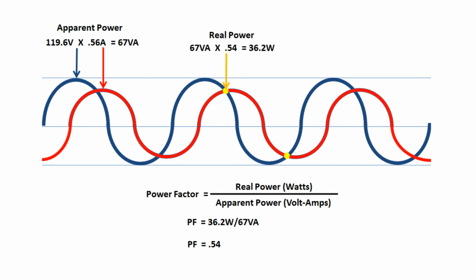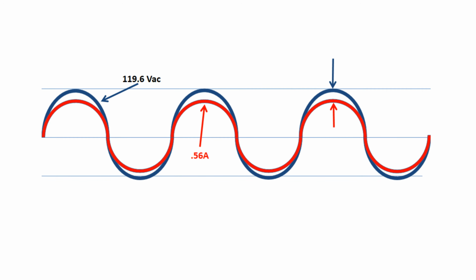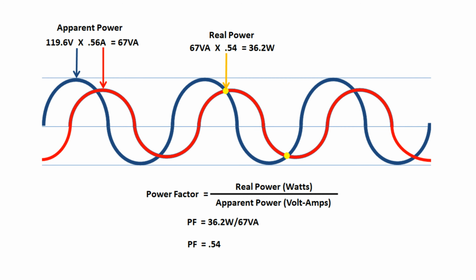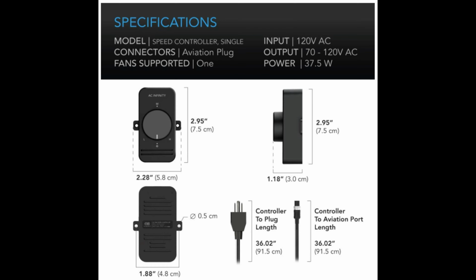The difference between apparent power and real power is basically just some wasted energy, because it doesn't do work. The higher power factor you have, the better. It's more efficient. But the important lesson here is that we always use volt amps when we're calculating loads for our AC circuits, because watts aren't always a good indicator of the current in the circuit. And the product specs I was using at first didn't provide the information I need, which is amperage. So the only good way to size this fuse is to measure the motor's actual high-speed current.